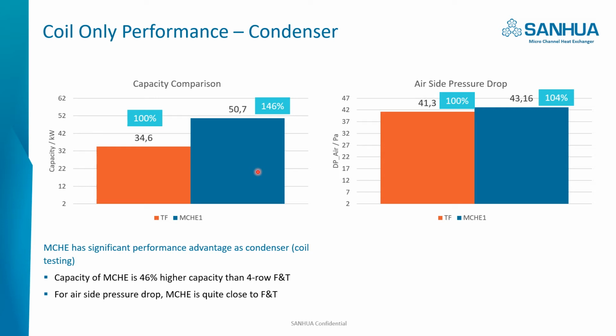We first tested the coil-only performance as a condenser. The left chart shows the capacity comparison of microchannel to fin tube. Microchannel is 46% higher than the 4-row fin tube heat exchanger. The right chart shows the air side pressure drop. Microchannel heat exchanger is about 4% higher, but generally it's the same level.